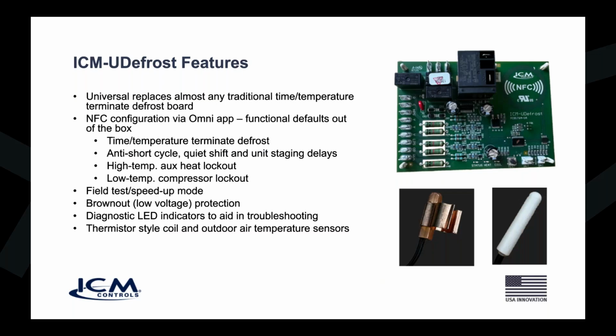The unit comes functional with defaults already out of the box, so it can sometimes be installed right away. Other times you might want to tweak it with the app. It has time and temperature terminate defrost, so it can terminate the defrost cycle on the coil temperature or a given period of time that you set. Say you only want the defrost to last for 10 minutes. Then at 10 minutes, regardless of the coil temperature, we're going to terminate that defrost. It has built-in anti-short cycle protection to prevent short cycling of the compressor, which could be very harmful to the compressor. We have a quiet shift feature. If anybody's ever had a heat pump where the reversing valve shifts, you hear a loud bang when that happens. The quiet shift prevents that from happening. We also have a high temp auxiliary heat lockout and a low temp compressor lockout for safety features.